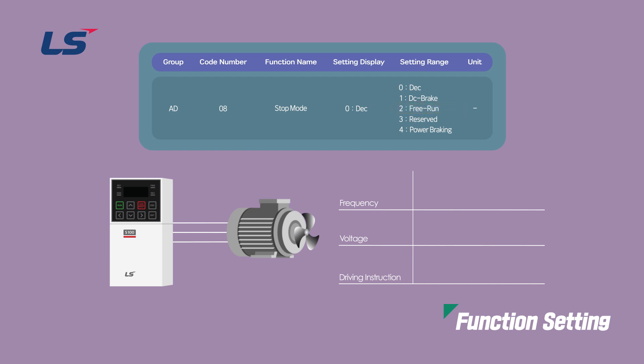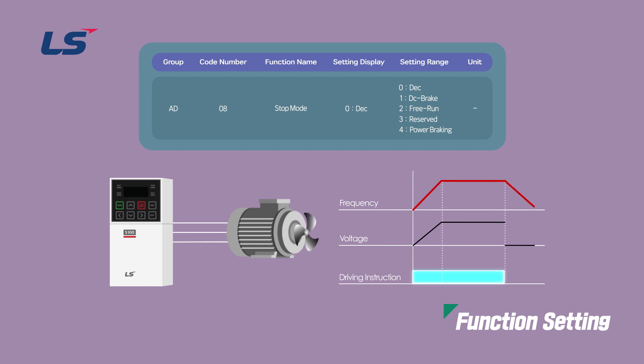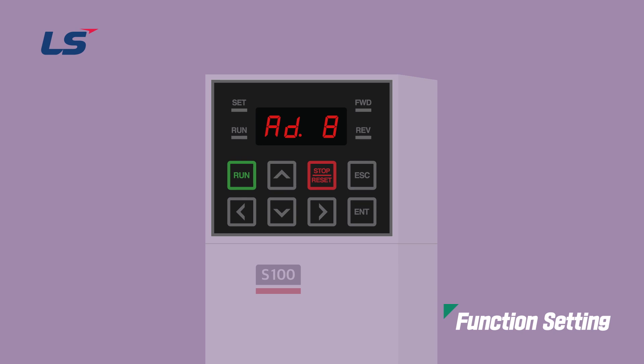The free run stop method is a function that cuts off the AC drive output when the operation command is turned off. Even if the AC drive output is cut off, the motor may rotate under the inertia of the load for a long time if the motor has large inertia and is running at high speed. Free run stop creates the same effect as a facility running on direct input. To set it using the keypad, at AD8 stop mode, press enter to bring up the stop method screen. Use the arrow keys to move the cursor to free run number 2 and press enter to finish setting the free run function.